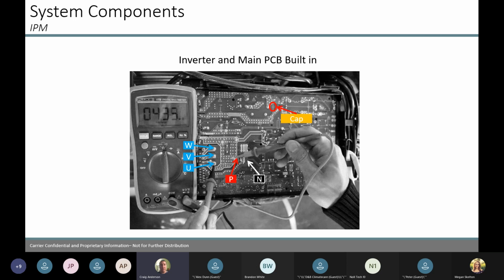You're going to see a board that's flipped upside down in the unit once you take the cover off. Be mindful, if the power is on to that unit, there's power on the back of that board. There are actually testing ports on the back of that board where you can test power going to your compressor and your fan motor. So if you take that cover off, don't rest your hand on there. You could get a little jolt. Everything will be labeled: your W, your V, your U that go to your compressor, and your P and N. So you can do some testing on the back of the board if required.